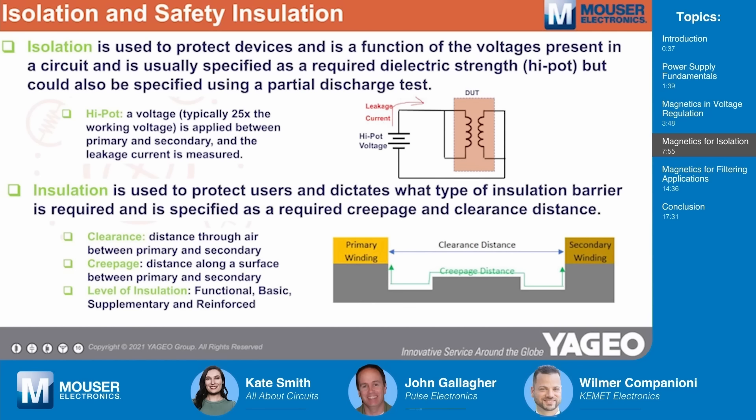The level of insulation matters as well. Functional insulation means we're just going to do a hi-pot test and not worry about creepage and clearance — typically used in low-voltage circuits. Basic insulation requires a little bit of creepage and clearance distance and a hi-pot spec. And then there's an increasing amount of insulation until you get to reinforced, which means there are two levels of insulation — one can fail and a second will still keep the system safe. Most offline high-voltage systems would use reinforced insulation.